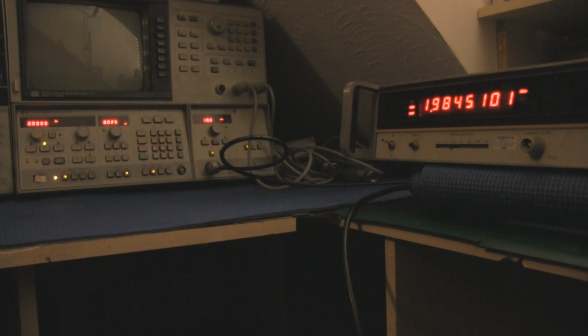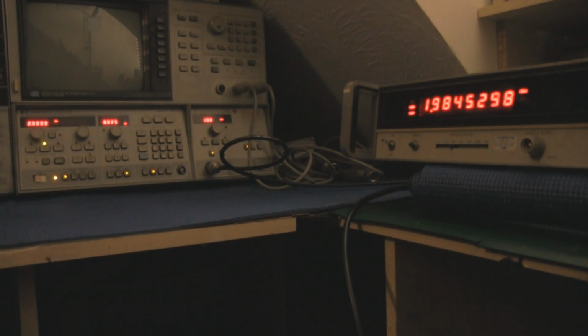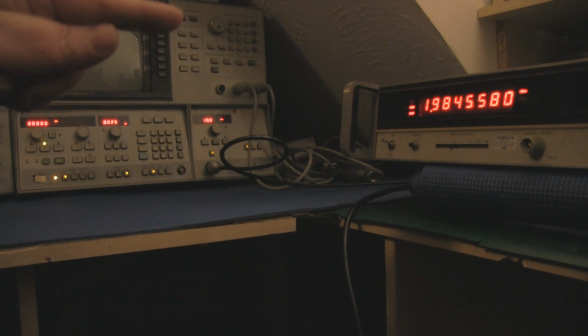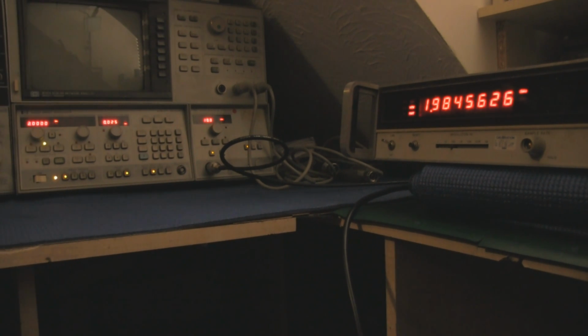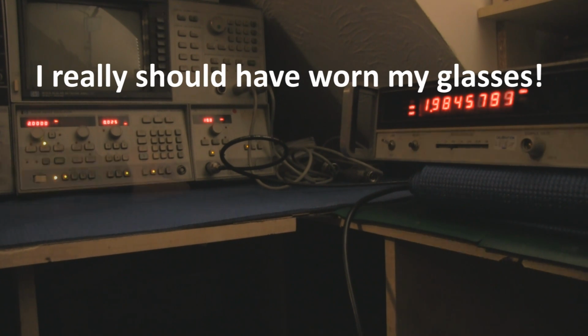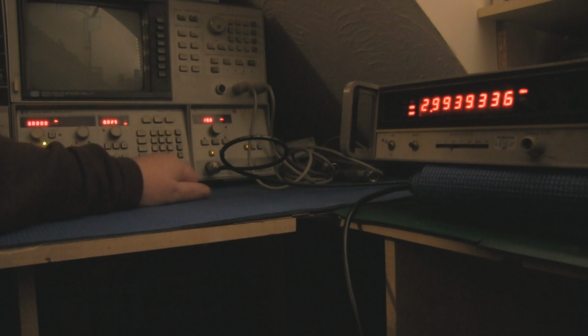So that may be a little bit of cable loss, because it does seem a little bit better than it did at the 1 GHz, but you know, if it's been sat in a cupboard for years and years, and it's an old piece of equipment, 30 years old, then the calibration is going to be out. And there is a calibration sticker on the front of the frequency counter, and it was last calibrated in 1994. So let's go up to 3 GHz then and see how well it handles that.